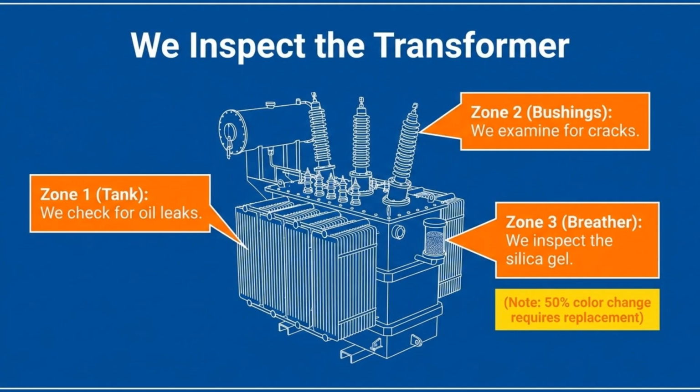Before testing, conduct a visual inspection. Check the tank for oil leaks, inspect bushings for any cracks, and examine the breather's silica gel. Remember, if 50% of the gel has changed color, it requires replacement.